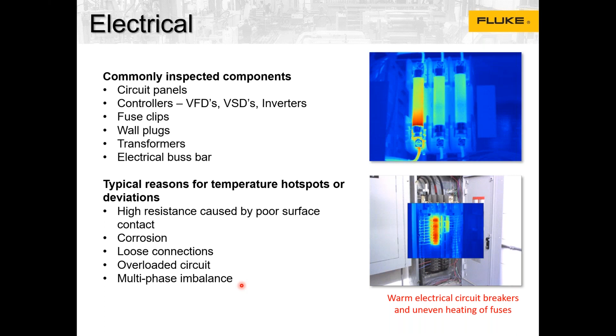So with a thermal camera, when you switch it on and focus on your panels, you can detect that there is a loss of connection. Overload and multi-phase imbalance can also be detected with the thermal camera. The thermal camera will give you the first sign of loss of connection, overload circuit, and multi-phase imbalance. If you have an overload or multi-phase imbalance, you can also use other products, like a power quality product, to identify what the problem is really coming from. Okay.